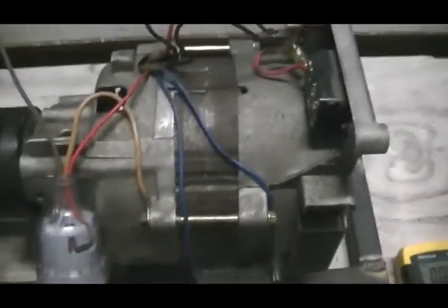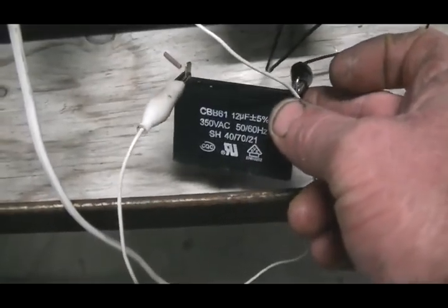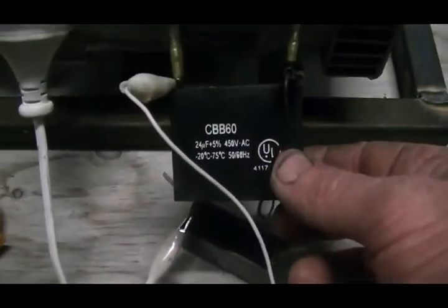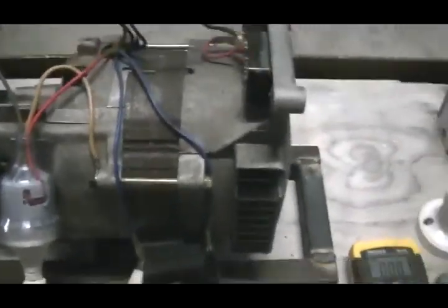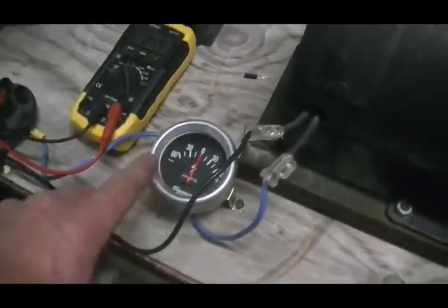So I have been playing around with it a little bit. It had this cap on the generator to start with, which is a 12UF AC cap. And I changed it around for a 24UF AC cap. And what that did was it gave me more output, but the draw on the prime mover came down. So I jumped the 12UF to give us a total of 36UF, and we got even more output. And our amp draw didn't go up.